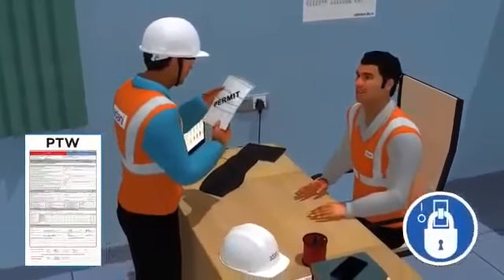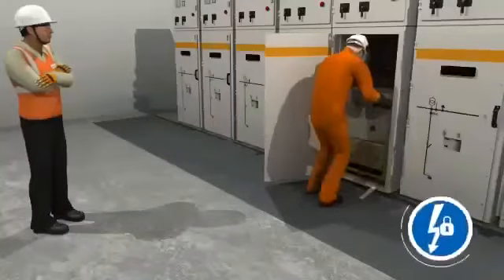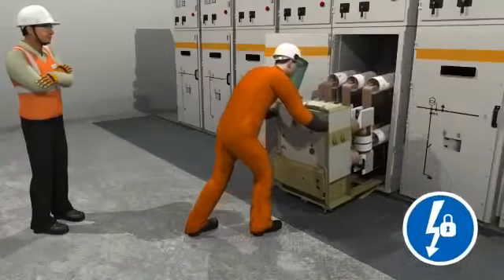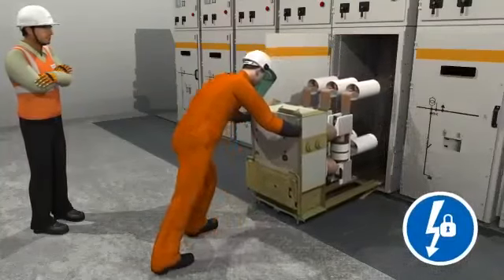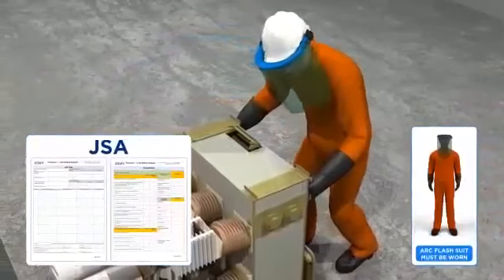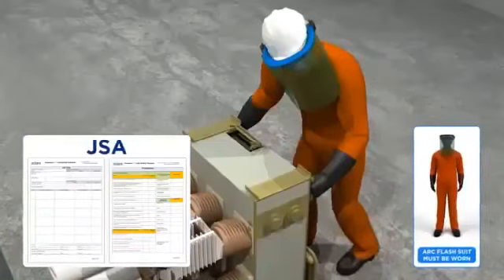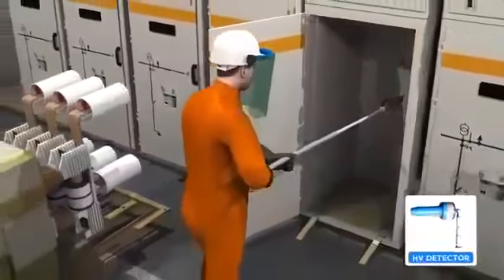Learning: PTW and LOTO must be taken for any electrical activities. Proper isolation must be done before starting work on any panel, in line with the isolation survey sheet. JSA should be followed at all times. An arc flash suit of sufficient rating must be worn while engaged in or near a live electrical panel. Use an HV detector to check the absence of voltage.